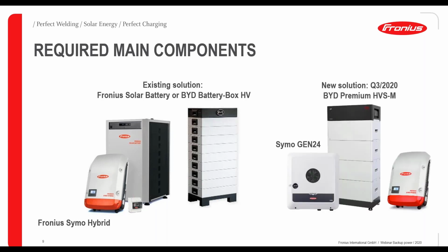For all new solutions, as of Q3 2020, we can offer as well a new inverter, the Symo Gen 24, and this comes also with the new BYD Premium HVS or HVM version. So we need here the high voltage version because it's a DC coupled system, and here you can use this new battery with the new Symo Gen 24 inverter. But you can also use, of course, the existing Symo Hybrid inverter, which is in a power class up to 5 kilowatt, and the Symo Gen is then for higher power classes from 6 to 10 kilowatt.